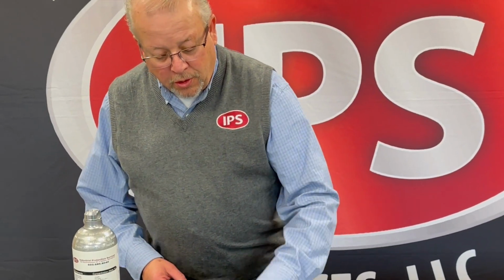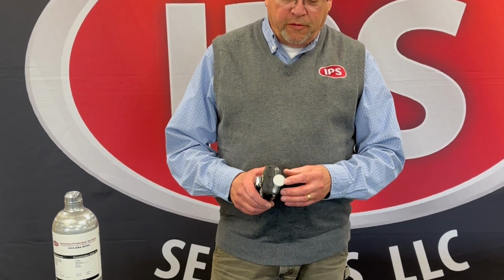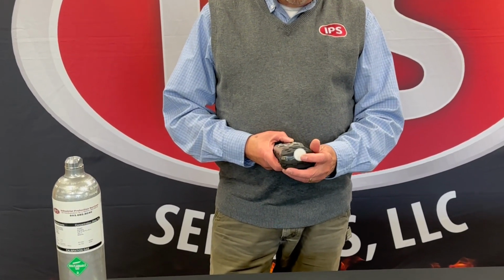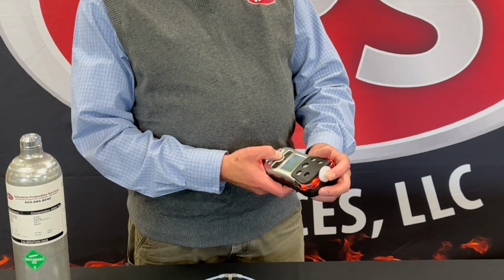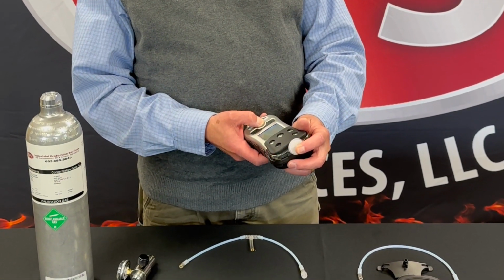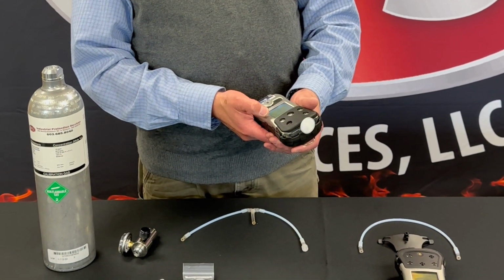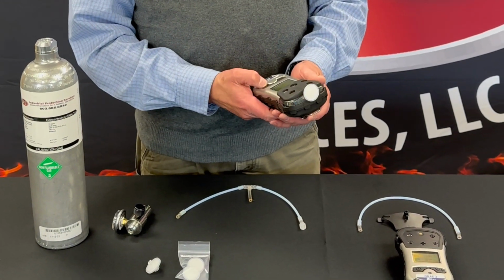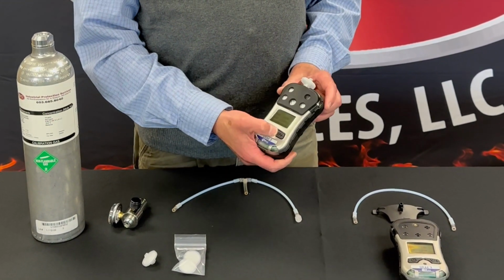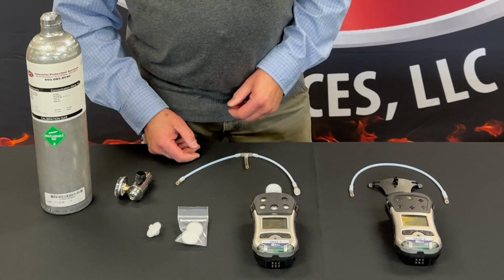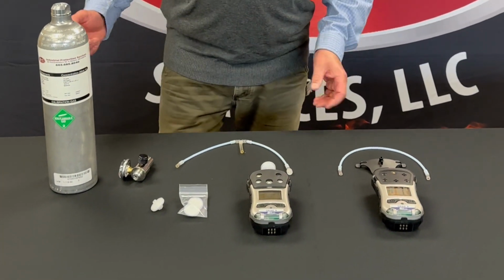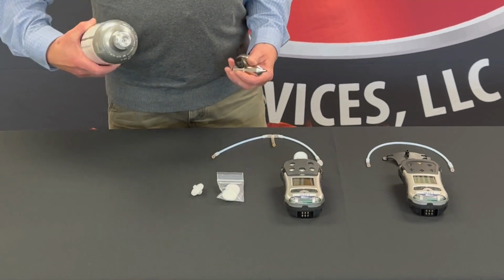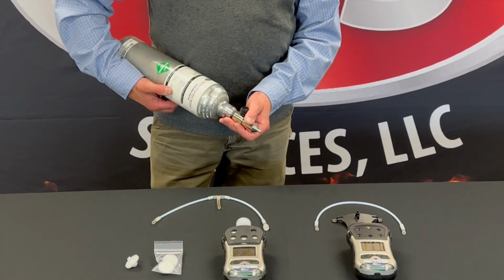Prior to doing your calibration, always check your filter. And while you're checking your filter, check the instrument to make sure that the pump is working correctly. You'll get that block pump indication. You can clear that by hitting the icon. I've confirmed that I've got a good operating monitor. Now I can assemble my calibration supplies and do a calibration.